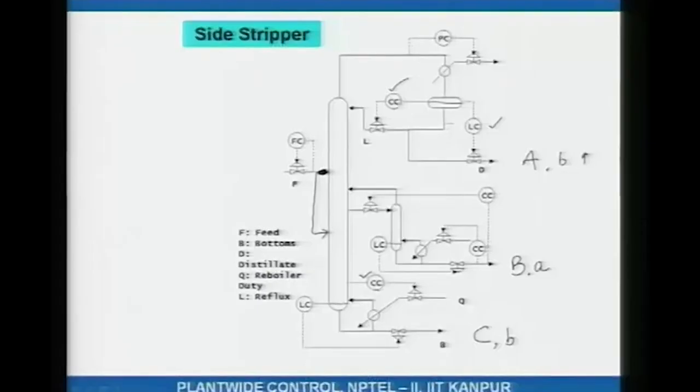What does this guy do? The purpose of the side rectifier is to not allow the A to leak down the bottoms of the side rectifier. So, if the composition of A in the bottoms from the side rectifier is increasing, you need to increase the reboiler duty, side rectifier reboiler duty. That is what this guy does. Okay.